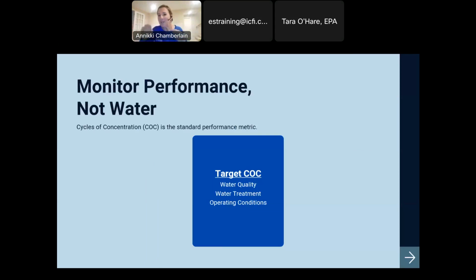So instead of chasing water use from year to year and day to day, the goal of a tower is efficiency, right? You're never going to get to 0 water. So let's use the efficiency, and as long as efficiency is in range, I don't have to worry about my water use as far as performance, because then I just know that's how much it needs to operate correctly. So we say, what's the target cycles of concentration? This is going to be different on every tower based on water quality, water treatment, operating conditions.